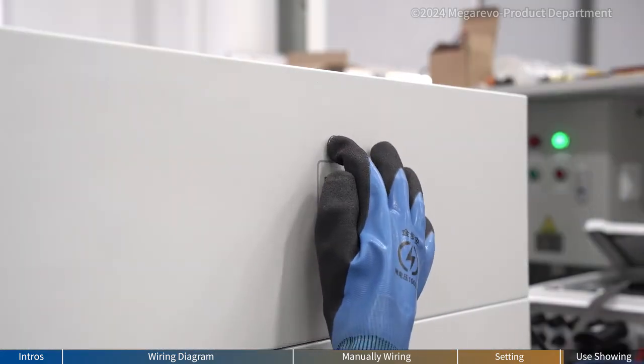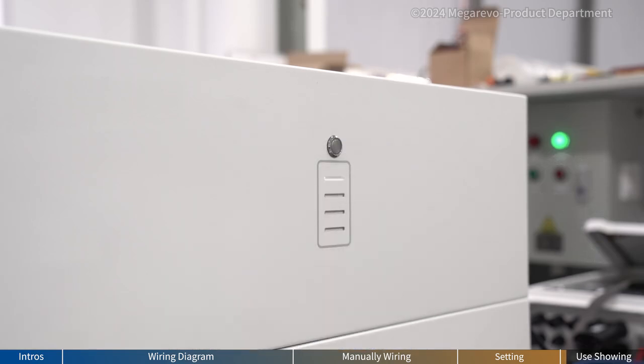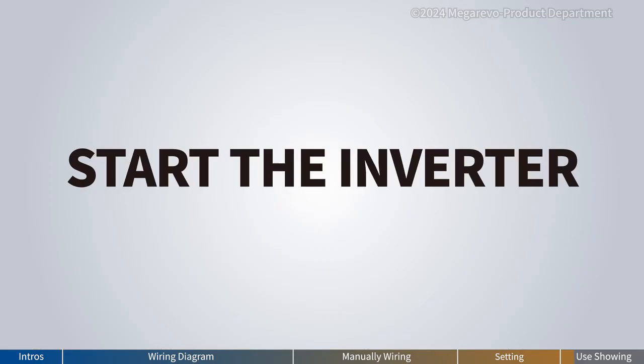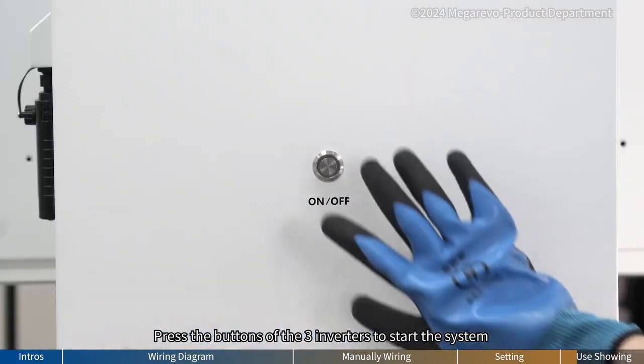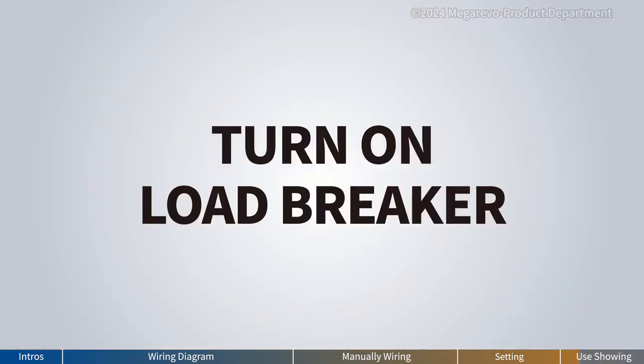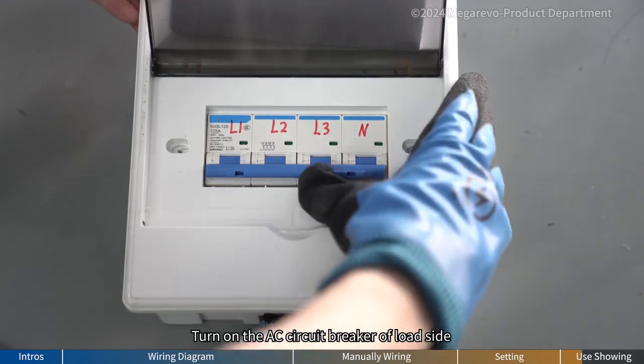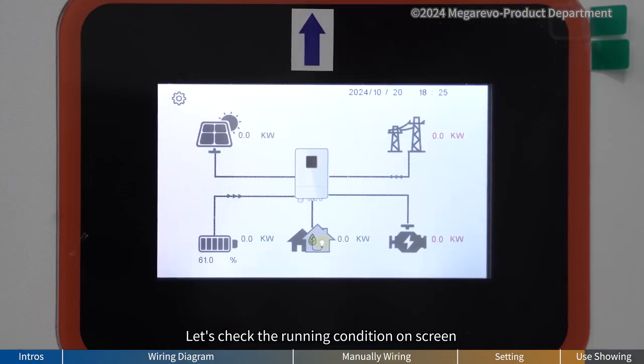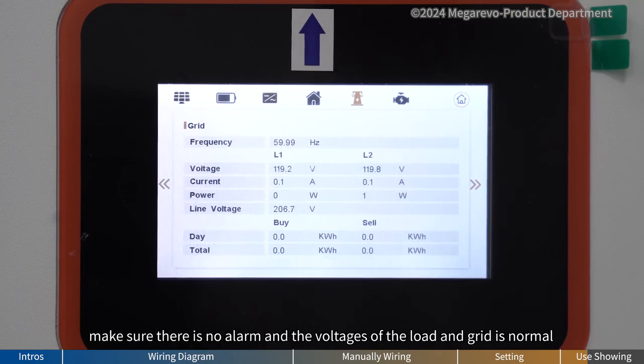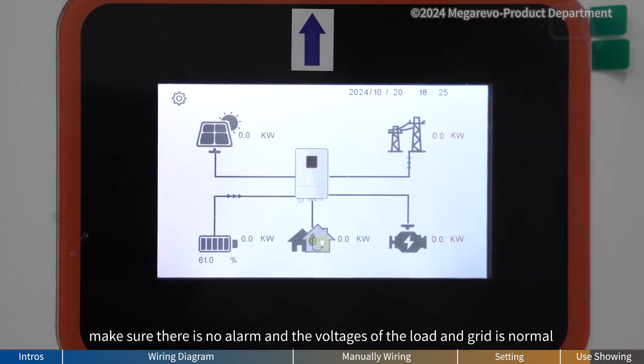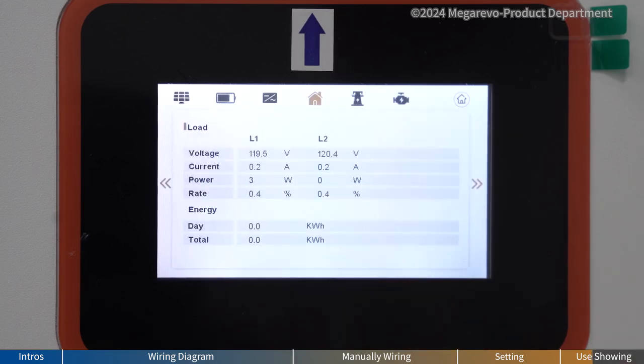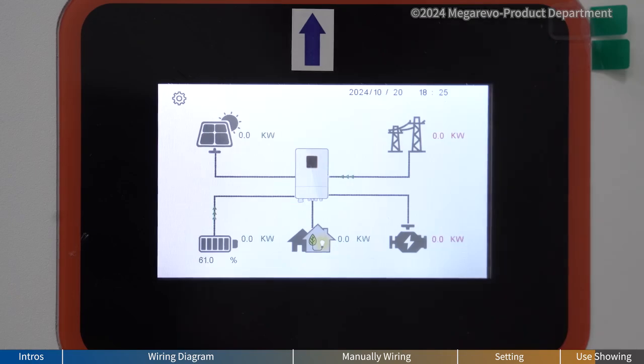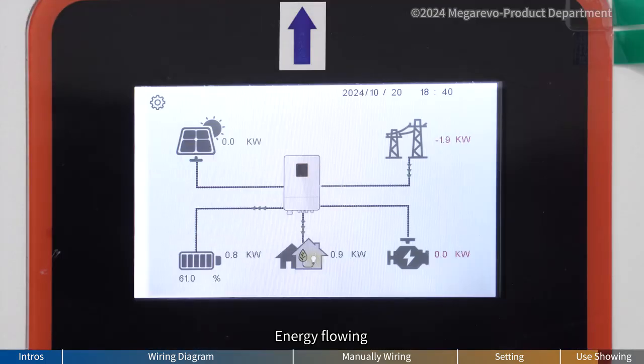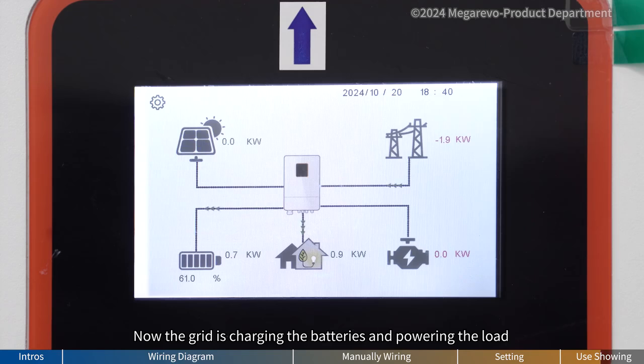Turn on the battery. Press the buttons of the 3 inverters to start the system. Turn on the AC circuit breaker on load side. Let's check the running condition on screen. Make sure there is no alarm and the voltages of the load and grid are normal. Energy flowing. Now the grid is charging the batteries and powering the load.